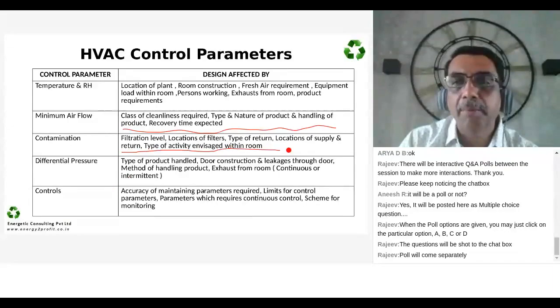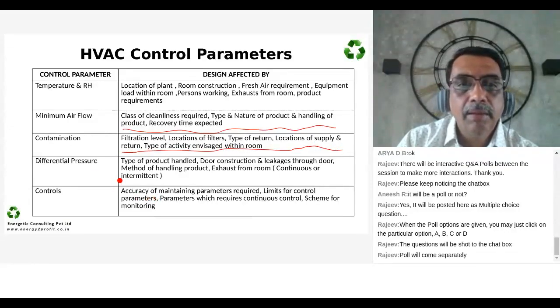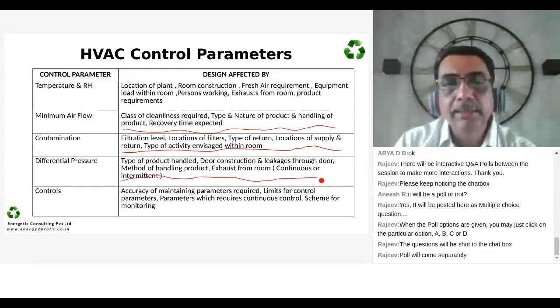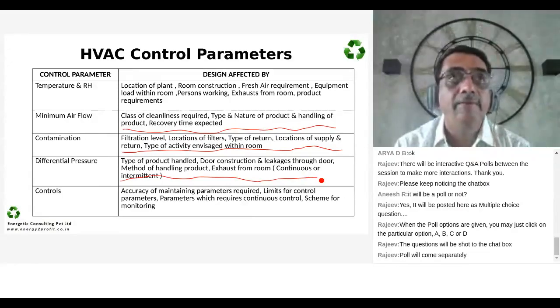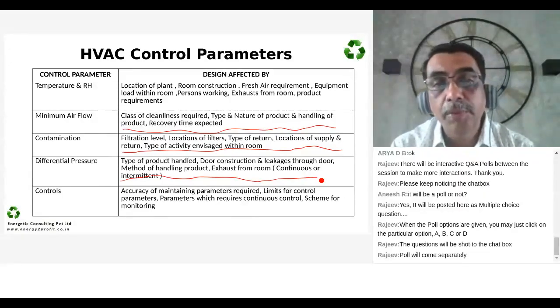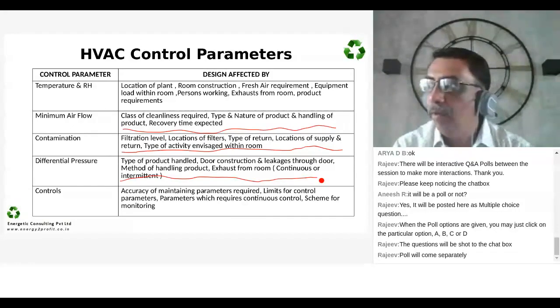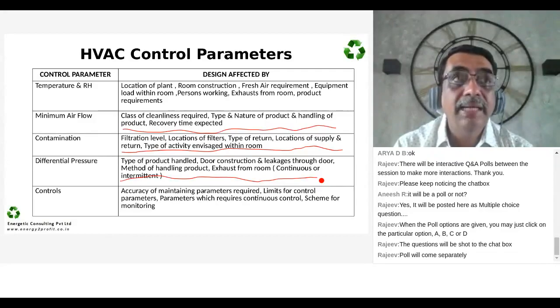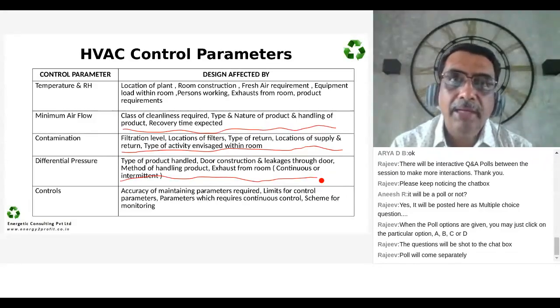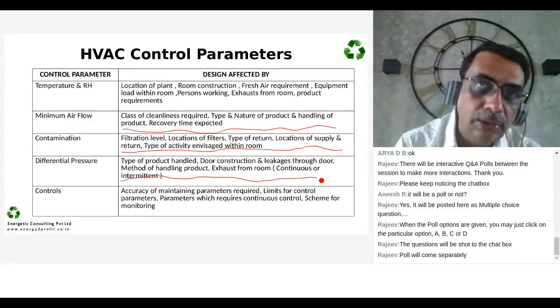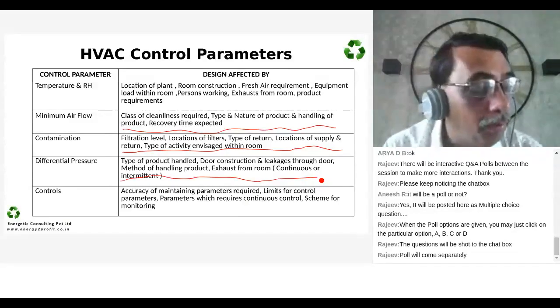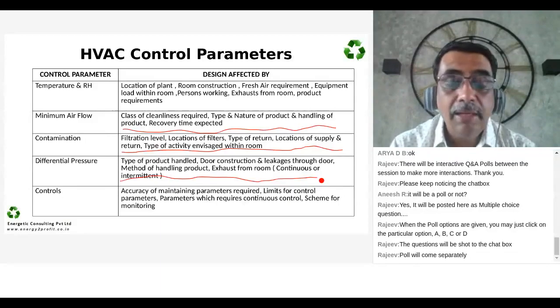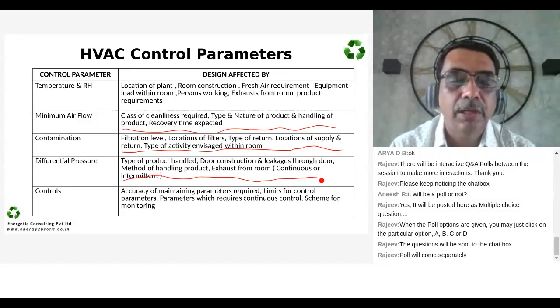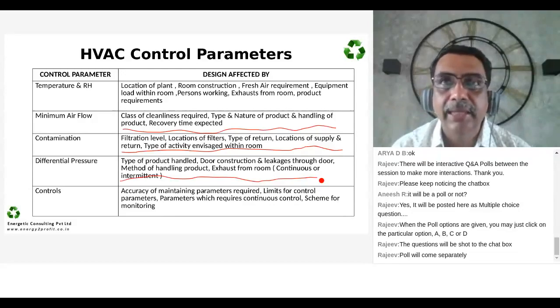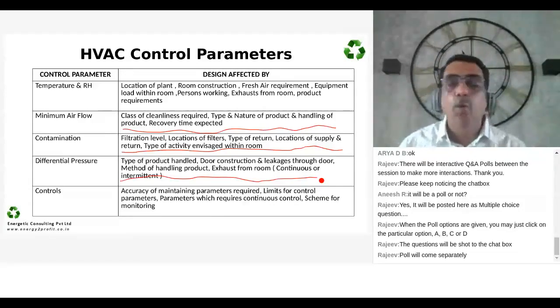Next part is the contamination part. Differential pressure control is specifically for areas where you have either dust or microbial contaminations, particularly pharma and hospital applications, which control the need for air conditioning. Which means that if you are making a drug, let's say a sex hormone or an oncological drug or a drug containing active microbes, the drug itself is a pollutant to the other areas, and the area in which the drug is handled has to be at a pressure lower than the surrounding areas. So in case of air leakage, air from other areas will come in and the drugs will not go out.